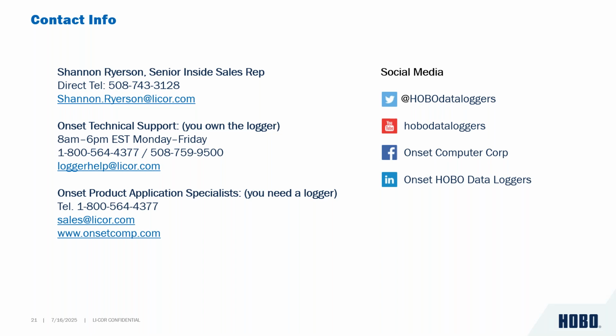We do offer NIST certifications, which gets you a traceable certificate showing that the device is within its accuracy range. All electronic devices do drift over time, but it's a minor drift. As long as you're using them within their intended design, you should get 10 plus years out of these sensors and loggers before they would need to be replaced. While you don't have to have them calibrated yearly, if they do go outside of spec, there's no way to adjust that calibration. You would need to purchase a new sensor.